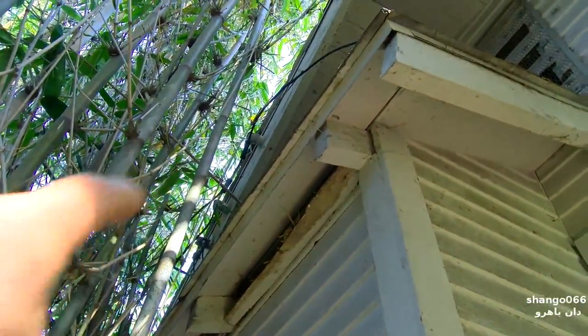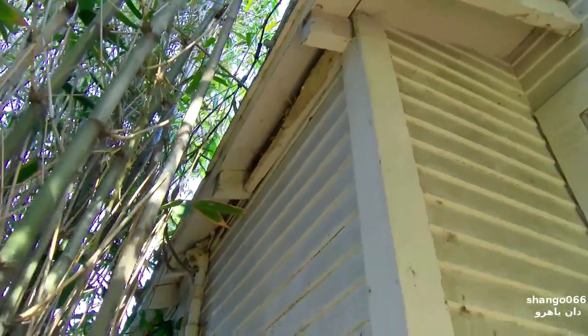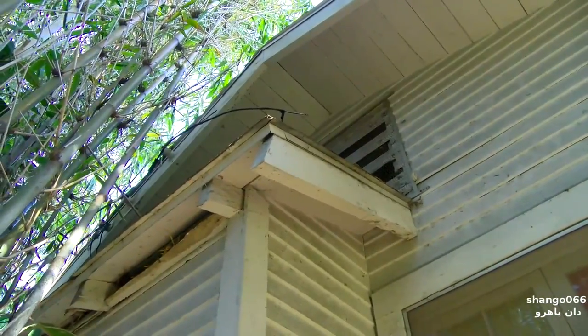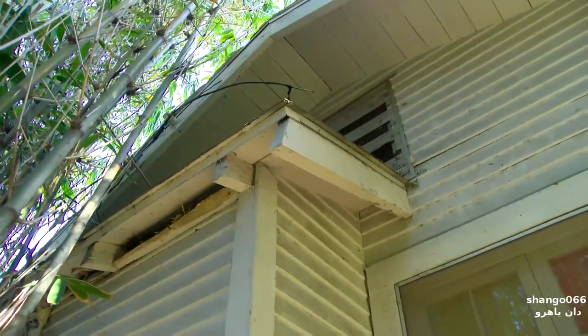I don't even think this is legal anymore — it comes out of the weatherhead and goes up to that second level of the roof where the utility was tied off. You can see that burnt area there. That shorted together, there's no fuse, and when I got called out here, this wire was literally glowing red for about a hundred feet to where it connects to the pole — smoking and on fire. It's a good thing I had a fire extinguisher because I probably saved this house.